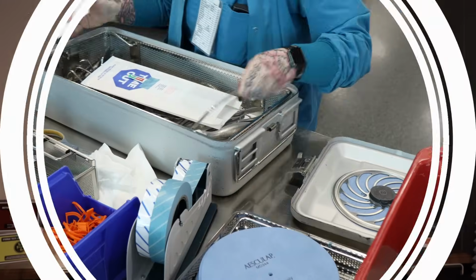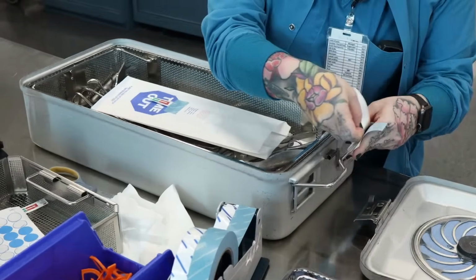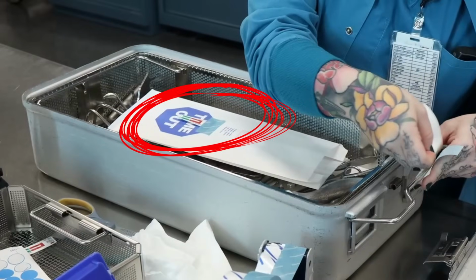These are placed inside the trays in specific locations depending on the packaging, and they prove to the operating room staff once they open the tray that sterilant in fact penetrated down to the instrument level. But wait, there's more to say about chemical indicators. But let's transition to the next section called the sterilization area first. Because sterile processing is very serious work, we don't only want to know the sterilant made it inside the trays, we want to know if the certain parameters were met, such as temperature, concentration of the sterilant, and time.